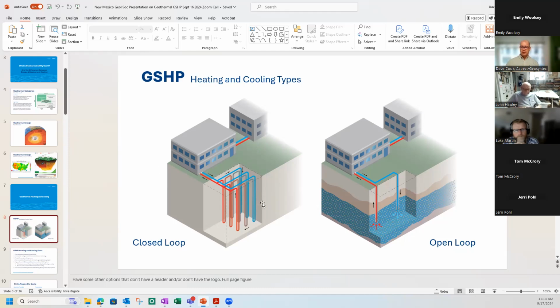Where these systems are most economically viable and super efficient is where mechanical engineers at the surface are looking at moving heating and cooling capacity across two different types of buildings. You can imagine if one building is in heating mode and another is in cooling mode and it's perfectly balanced, you don't need the ground. You can do all that work mechanically. That's usually not the case. That's usually out of balance. And so we're tapping the ground to supply that difference, either as a base load or for certain peaking events for heating and cooling. So that's how ground source typically works with heat pumps. That's the closed loop system.